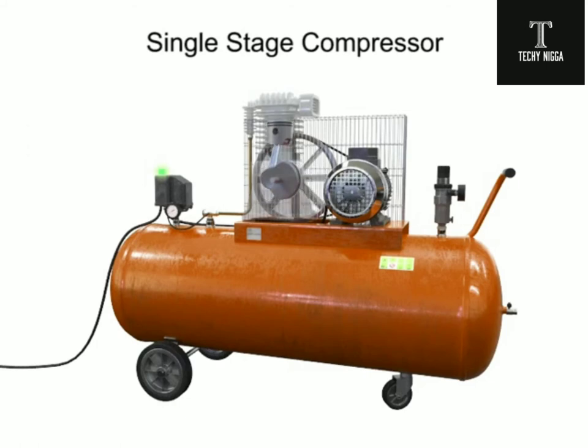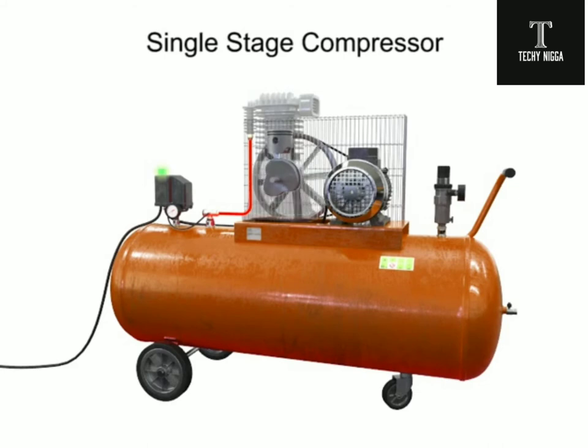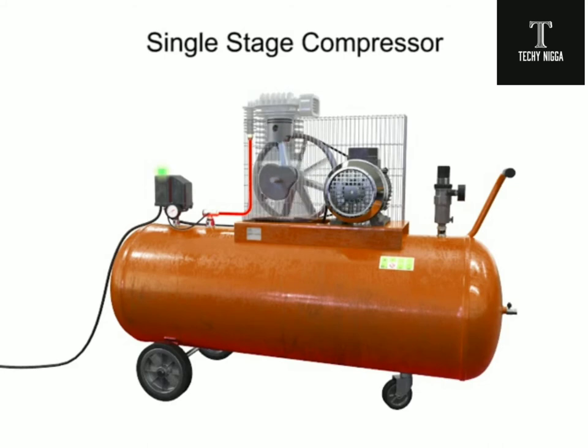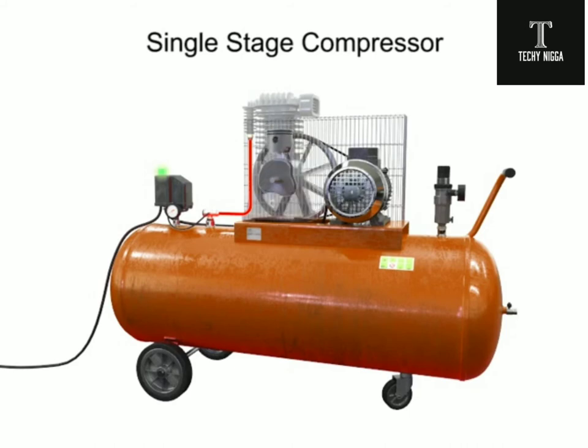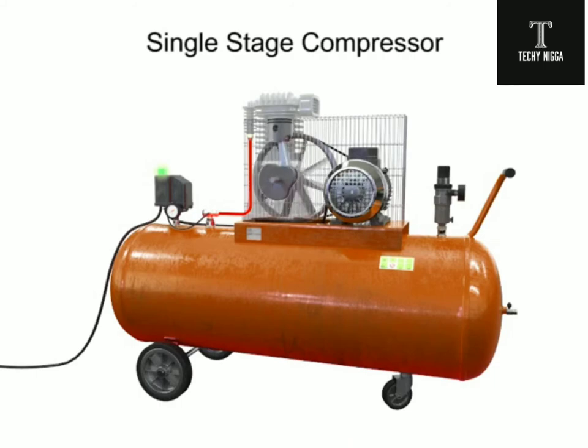As air is compressed, it becomes increasingly hot. If the air becomes too hot, not only is the compression cycle less efficient, but there is the hazard of an explosion if any hydrocarbon material, such as oil or lubricant, comes into contact with the overheated air.